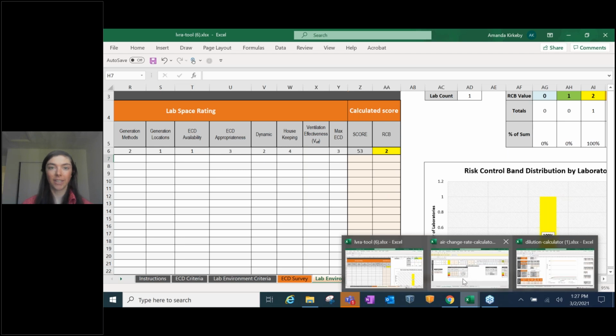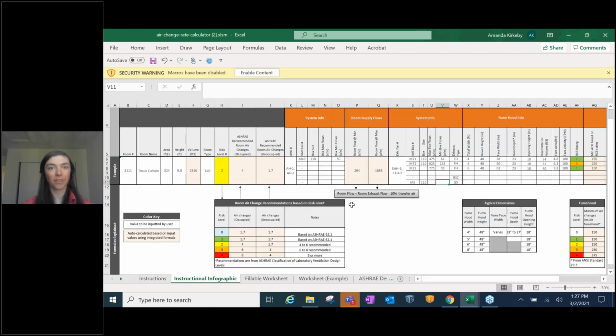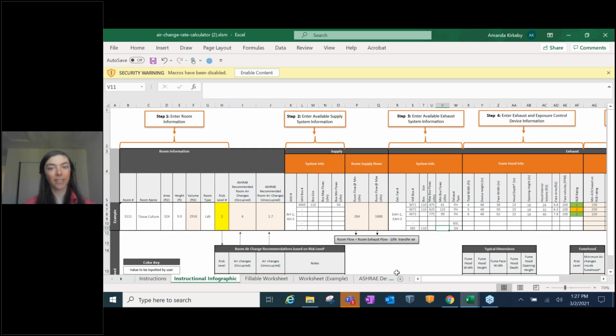You can use those scores as input into our air change rate calculator, which helps you calculate what air change rates you need to provide a safe environment for those specific research activities. It provides a systematic process for identifying those rates, so you're not providing more air than you need, spending more energy and money running ventilation systems at higher air change rates than necessary.